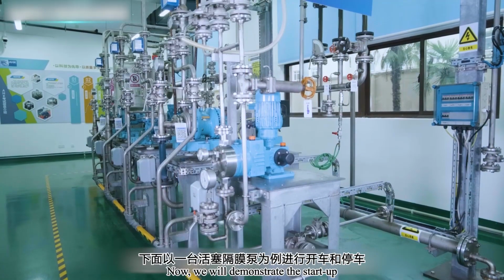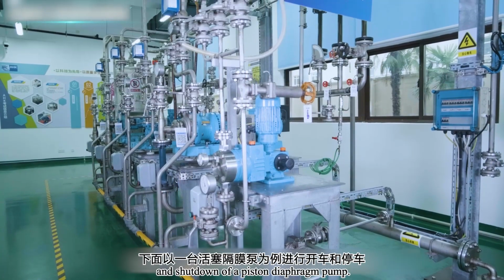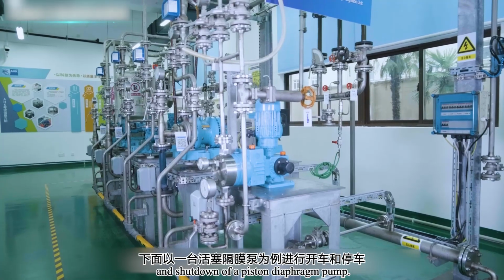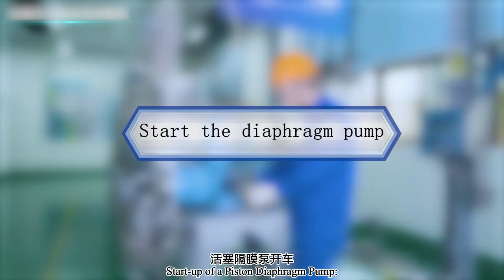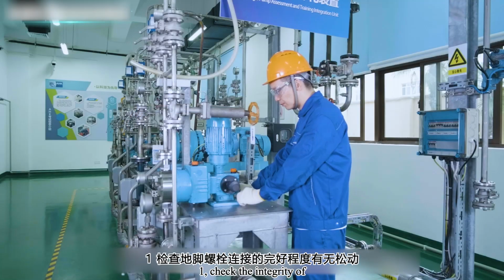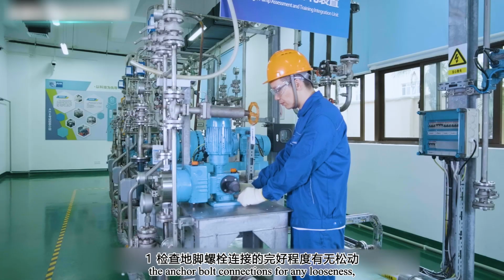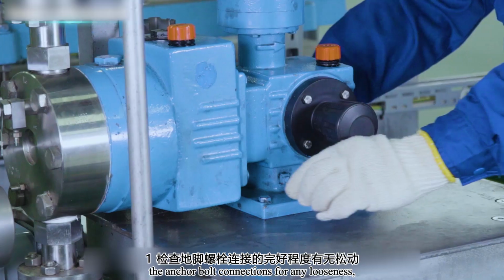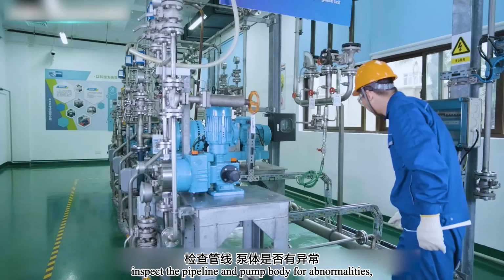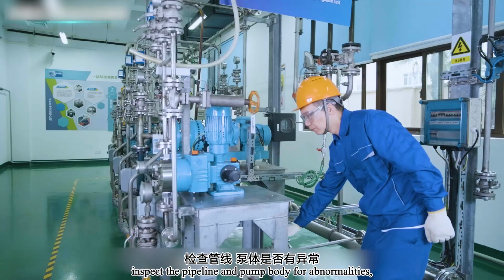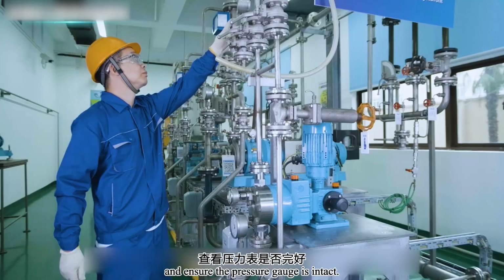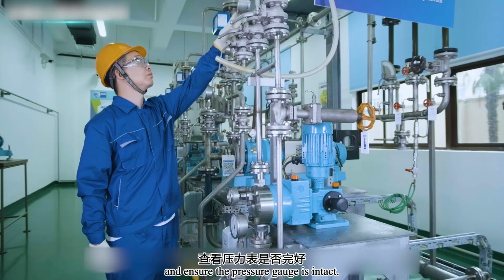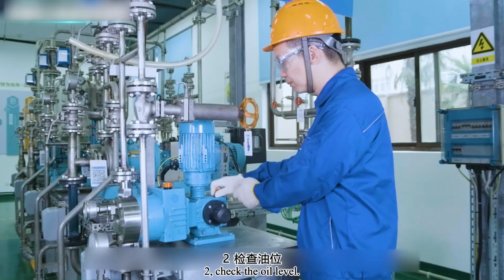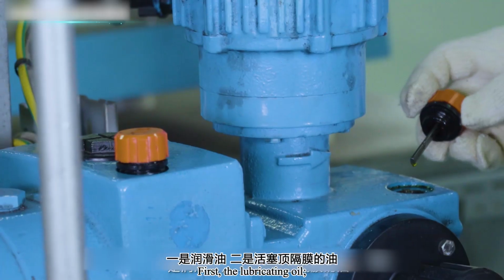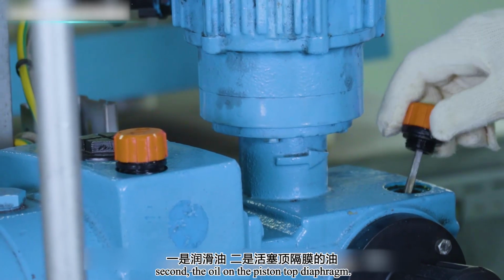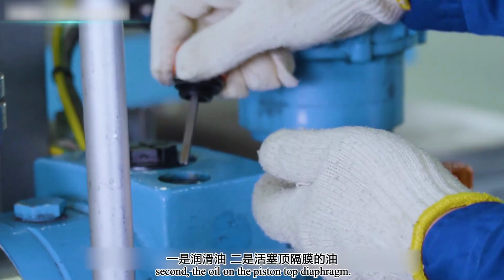Now we will demonstrate the start-up and shutdown of a piston diaphragm pump. Start-up of a piston diaphragm pump. First, check the integrity of the anchor bolt connections for any looseness. Inspect the pipeline and pump body for abnormalities, and ensure the pressure gauge is intact. Second, check the oil level. First, the lubricating oil. Second, the oil on the piston top diaphragm.